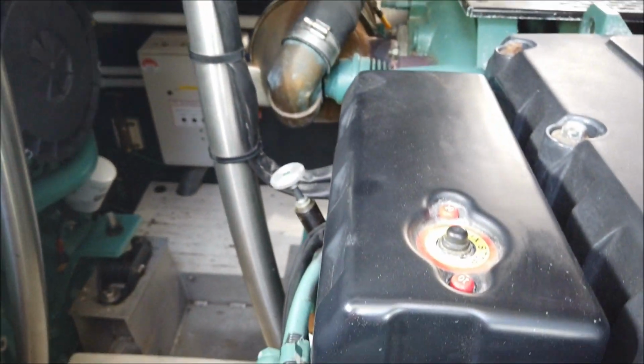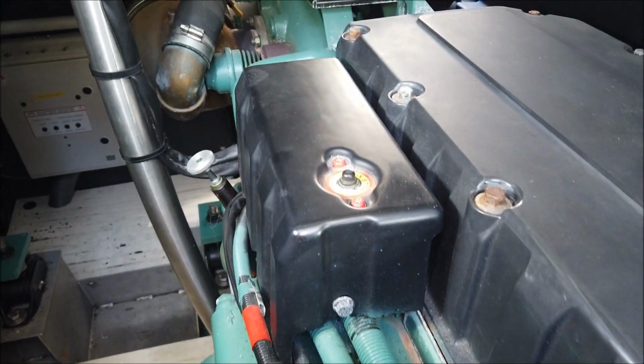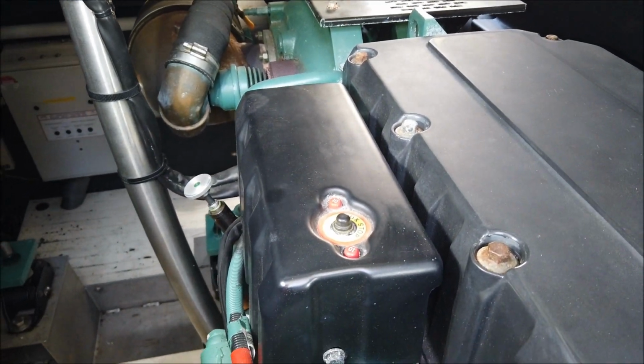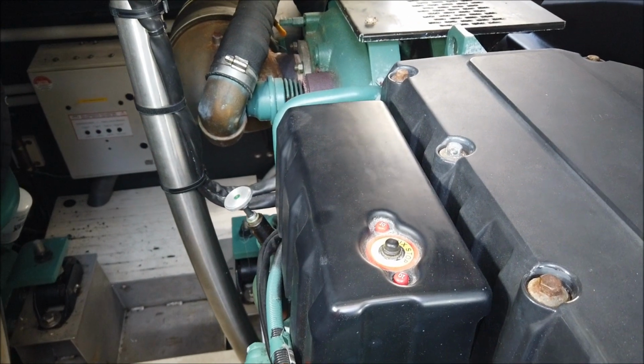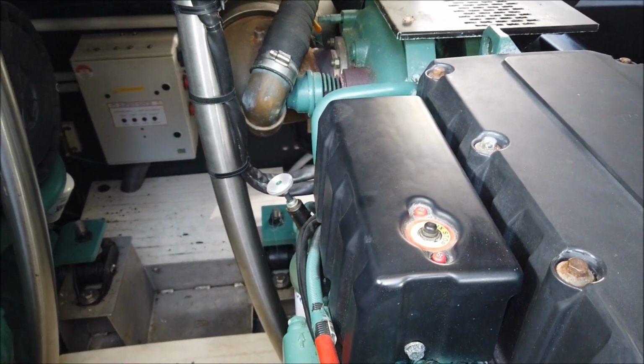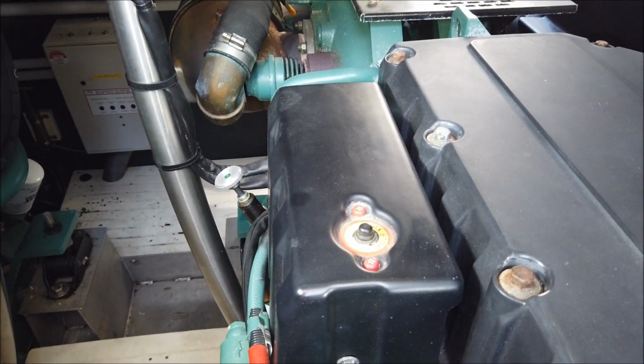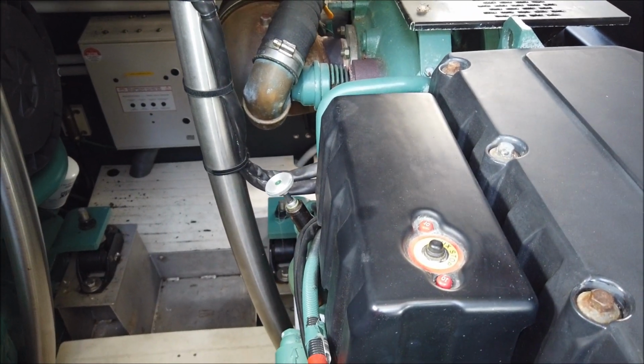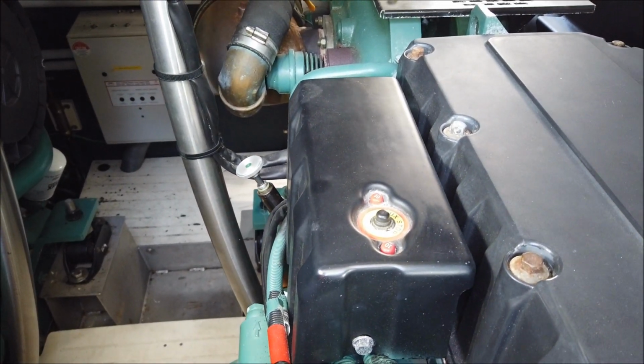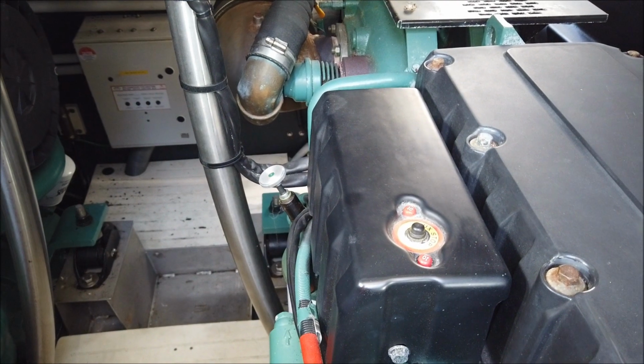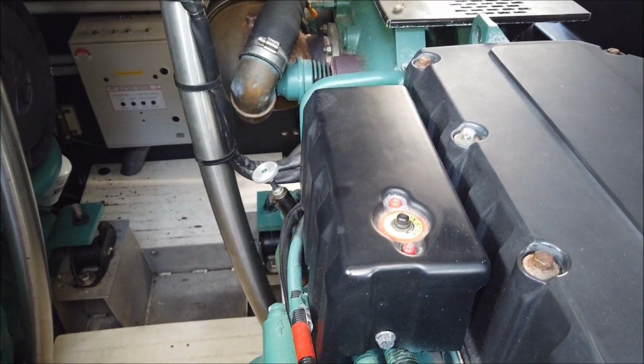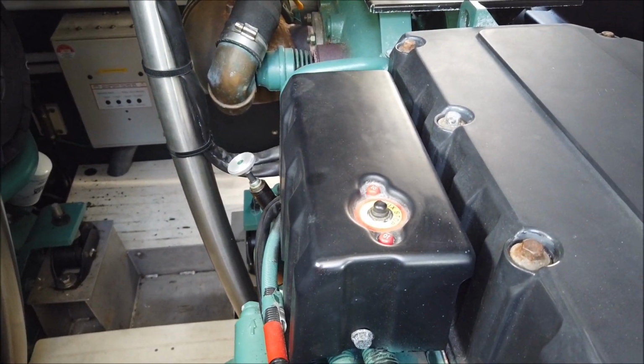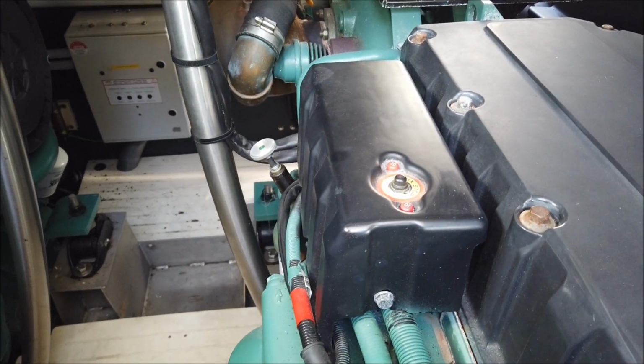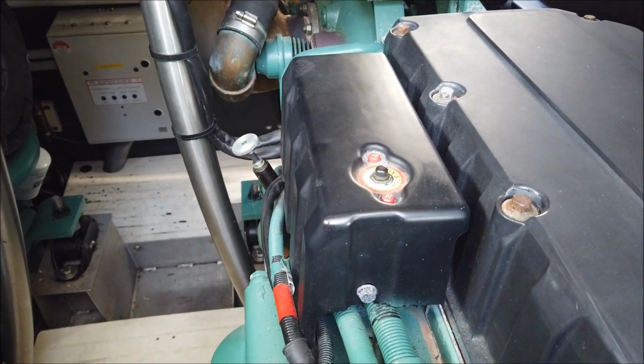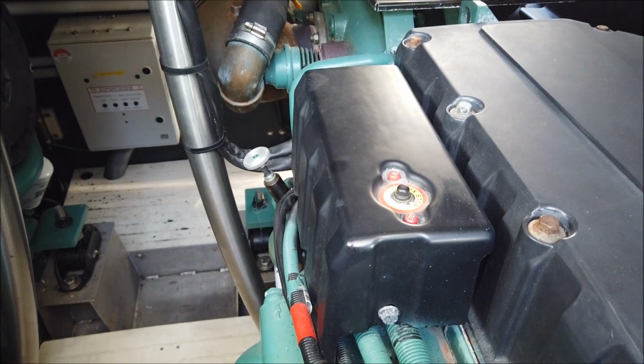In here, this black box that you can see with the auxiliary stop on top of it, that's an emergency stop should you be in here and need to shut the engine down. Underneath that box there are three relays, three 24-volt relays that control the starting and stopping of the engine. And if the D800 has a vulnerable spot, that is it.